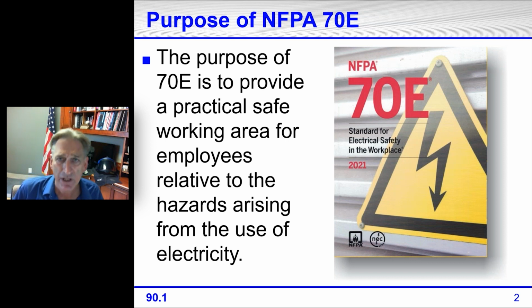All right, so what is the purpose of 70E? It's from NFPA, the National Fire Protection Association. NFPA has over 300 codes, recommended practices, and standards, of which NFPA 70E is a standard. The purpose of 70E is to provide a practical, safe working area for employees relative to hazards arising from using electricity. The National Electrical Code is an installation code. It gives us requirements for installing electrical conductors and materials. Once it is all installed, NFPA 70E takes over, and it gives us rules, regulations, and stipulations to keep us safe in the workplace.